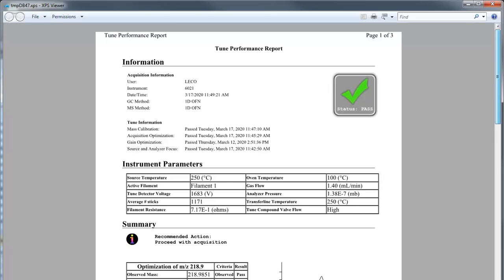These tune performance reports are full of valuable information displayed in the following sections. The acquisition information lists the user, instrument, date and time, GC method, and mass spec method used while acquiring data for the tune performance report. The tune information lists the current optimizations associated with the mass spec method. These optimizations include the source and analyzer focus, gain optimization, acquisition processing optimization, and mass calibration.